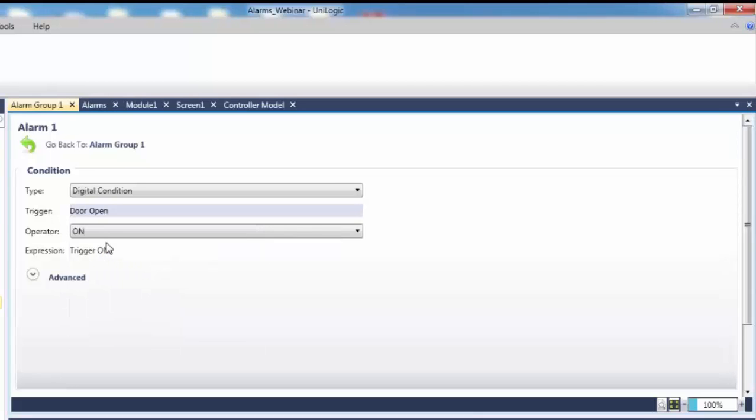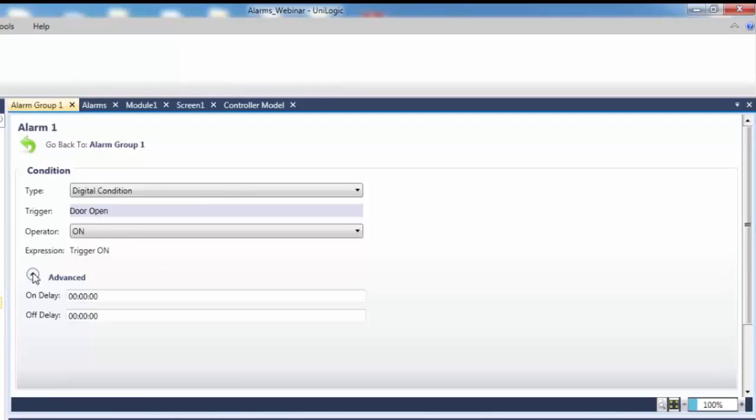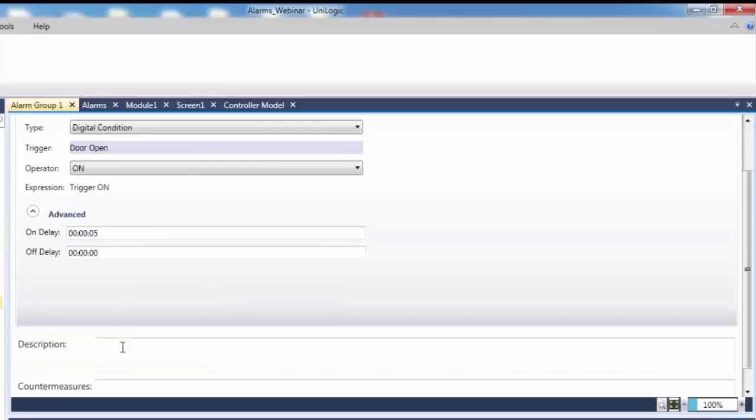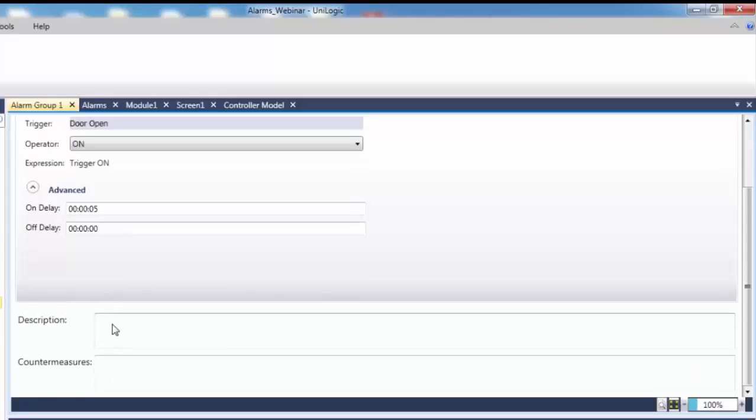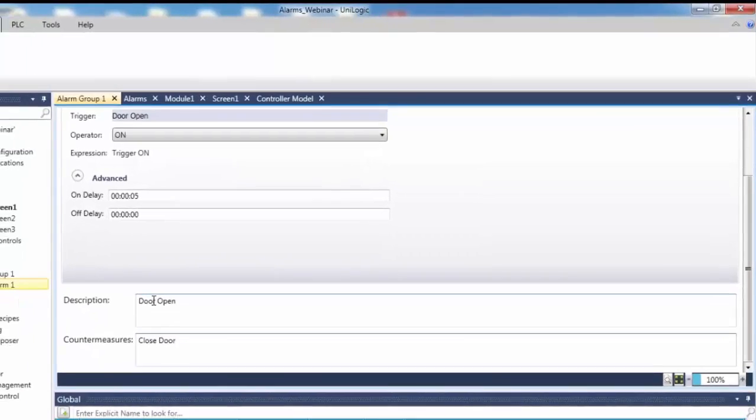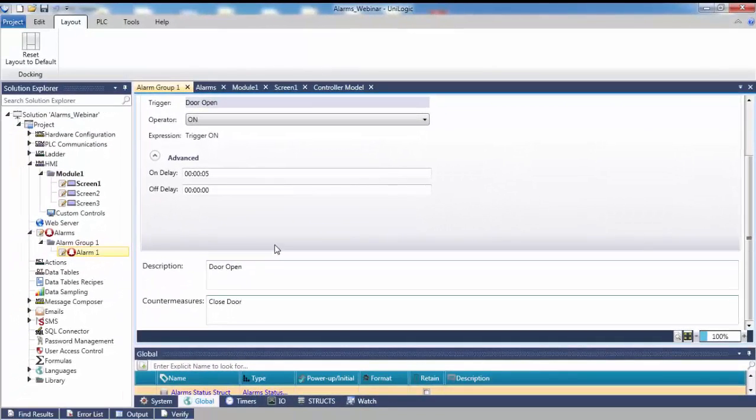Next, navigate to advanced options by clicking the advanced down arrow. Here, a delay time can be added before the alarm is triggered. In this example, the goal is to have the door open for 5 seconds before the alarm triggers. Set the on delay to 5 seconds. Below the advanced options are the alarm's description and countermeasures for the operator. The description and countermeasures provide additional information to the operator and help them resolve the active alarm condition. The digital door alarm is now complete.